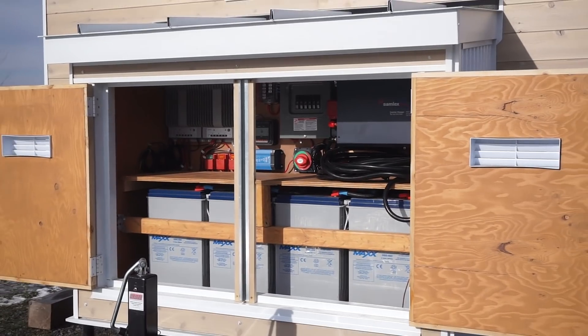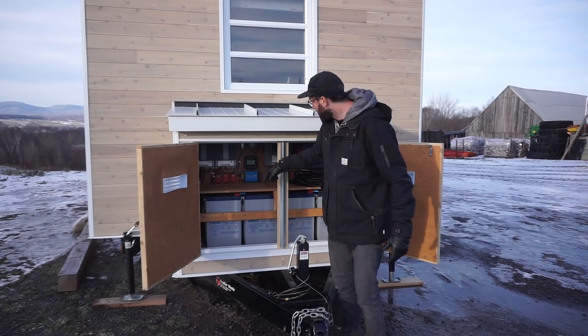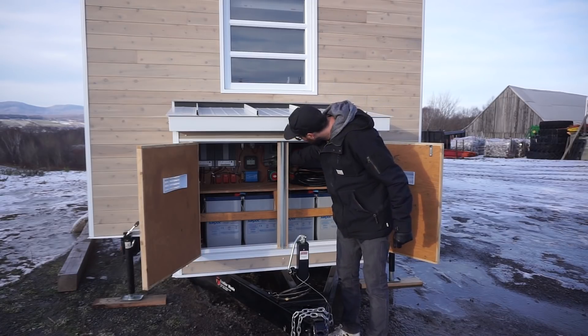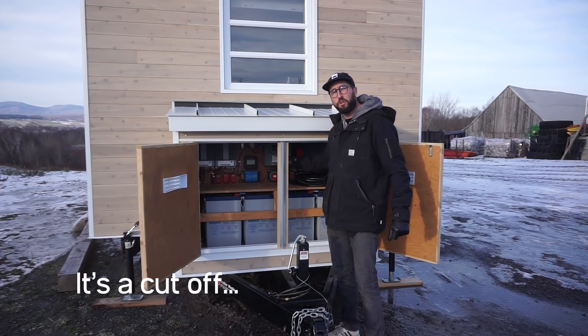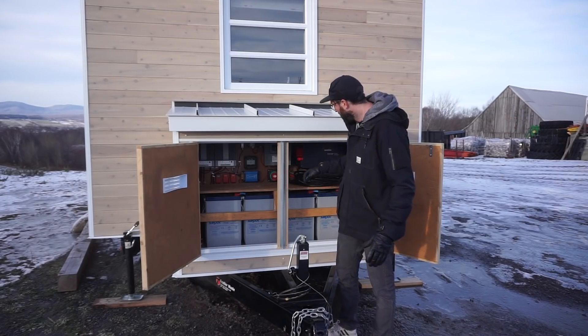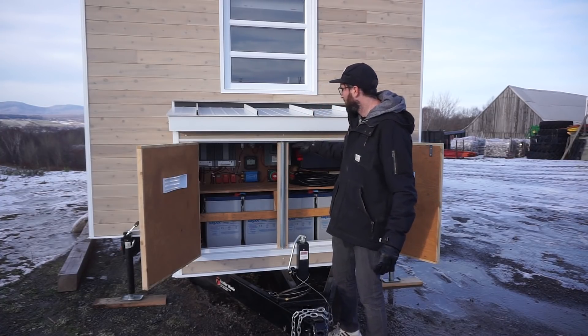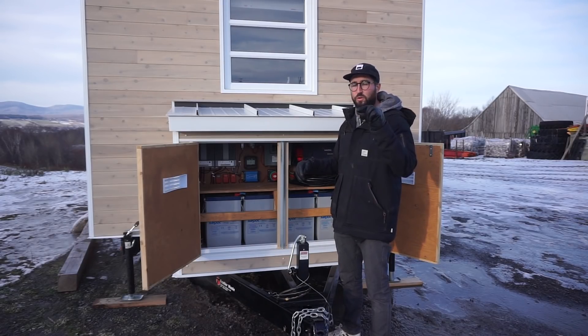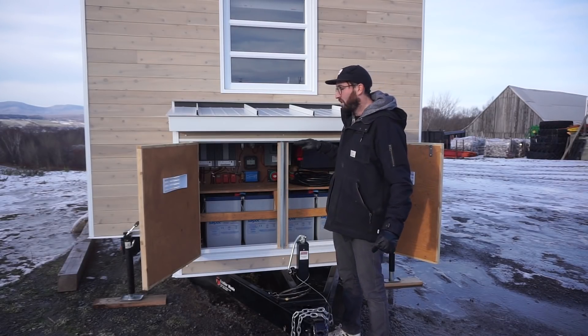The batteries are 24 volts. When I need 12 volts, the power comes out of the batteries and goes into a 24-to-12 volt converter. Then it goes into what we call a knife switch — it's basically an on/off for the 12-volt system. If anything happens and you want to shut off everything working on 12 volts, you open this knife switch. After that, it goes into the fuse box, where you have all the fuses for every circuit.